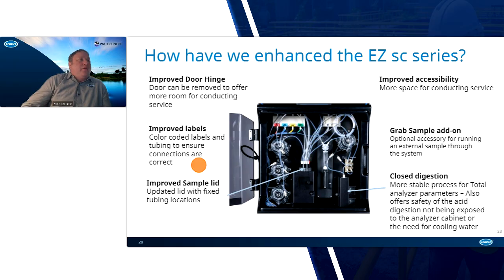We do have improved labels. If you look here at the micro pumps, these are where the reagents are coming in. Your reagents are going to be located below. It allows you to make sure that there are no cross connections and that everything is easy to follow within the systems. Same goes for the improved sample lid and colorimeter, where the trajectory from the micro pumps into those vessels to introduce the chemistries is much easier to maintain and much more secure. Before, the colorimeter could move around a little bit. If you have used our spectrophotometers in the lab, like Lamy had shared before, a little bit of movement, especially on the sensitive parts per billion analysis, can lead to some variability in the number. So this is much more secured.